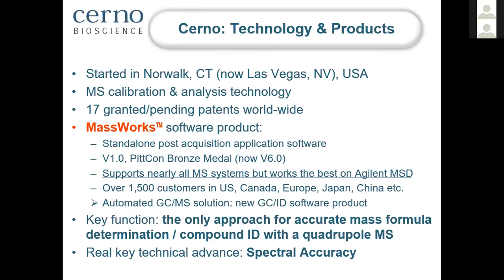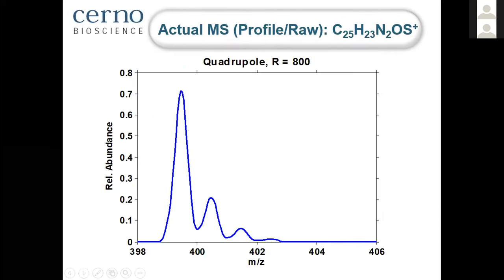To give you some basic ideas for those of you who are not familiar with the technology. In mass spectrometry, whenever you turn the mass spec detector on, the detector is busy collecting signals. As the ions arrive at the detector, in this case the monoisotope arriving and disappearing, the detector faithfully records the arrival and the disappearance of that particular ion. It has a spread in a tiny region which defines the resolution. And then it faithfully records the arrival of the plus one and the plus two, in addition to its spread, of course, and the plus two and the plus three. So the detector records full profile raw data continuously, nonstop.